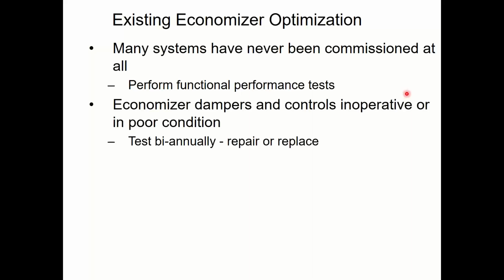Okay. From an economizer standpoint, remember I said I'd like to maintain the building 5 times a year, the equipment 5 times a year, or excuse me, 4 times a year. A couple of those times should include maintenance on the economizer. I like to cycle the damper all the way closed, all the way open, make sure it doesn't get bound up, make sure it physically moves. I like to double check the minimum airflow set point, and I want to check the sensors on that guy. Every 2 out of 4 times, right? So twice a year. Once going into the cooling season, once going into the heating season. I like to check it both times. Because if it's stuck open in the winter, it's sucking air and I don't want that. If it's stuck closed in the spring, I'm not getting the free air that I want. Right?